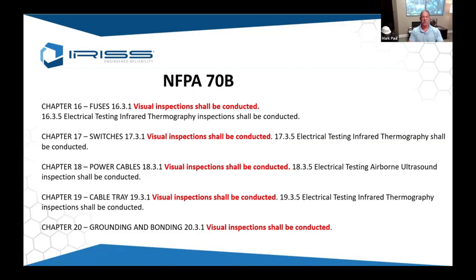Some of these require visual inspection, some require visual and thermography. If you just did a visual inspection, opening the panel door and taking a quick look, you're most likely not going to see much beyond something major like a wire hanging loose. But if you had thermoclips or paint on different components in that panel, during a visual inspection you would actually see, hey, we do have an issue here, we need to look deeper. It could save you a tremendous amount of money and potential downtime, or a condition that could cause an asset failure or a human life condition.